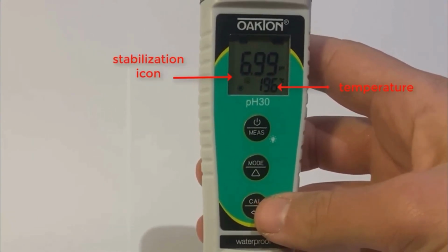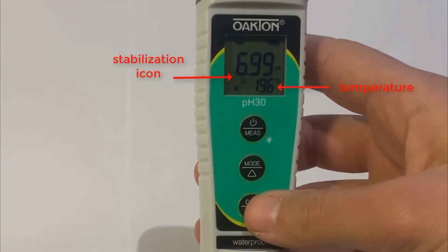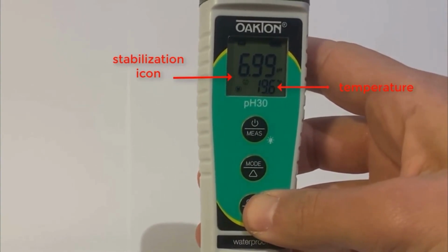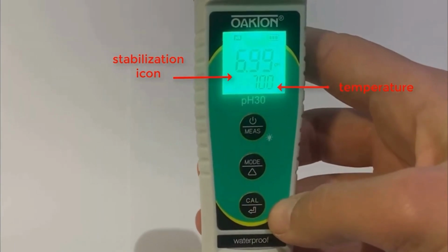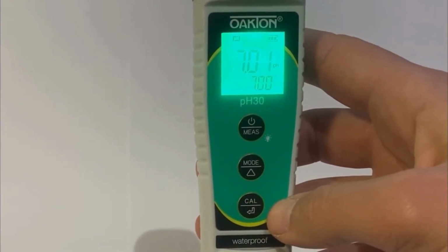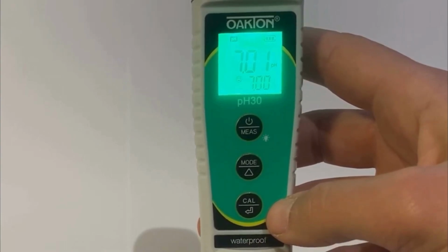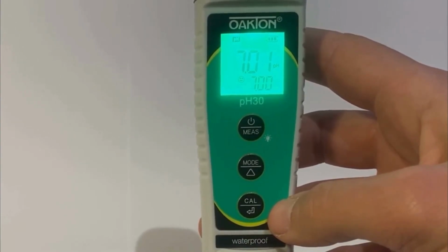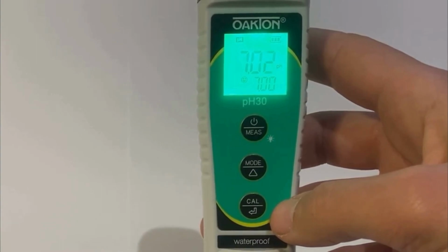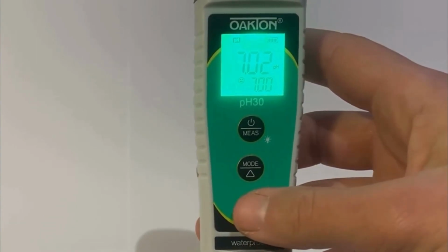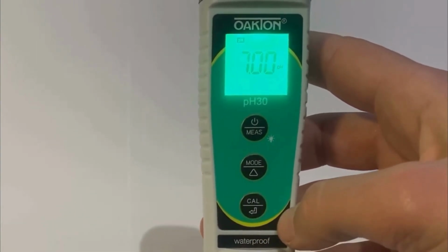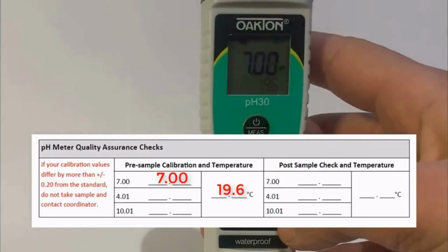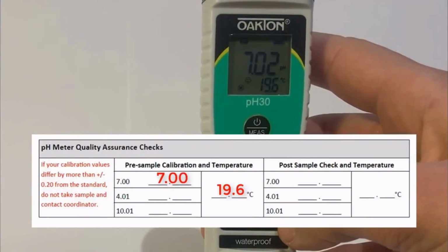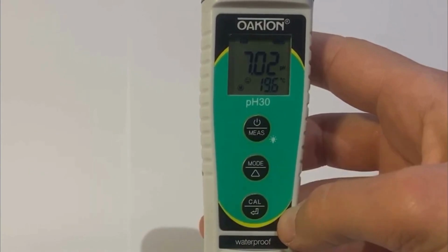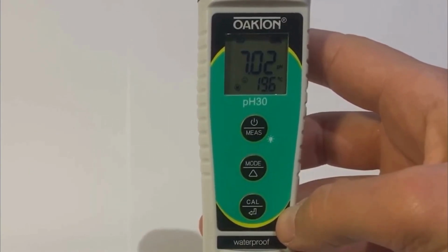Long press CAL, which is the bottom button, until your screen flashes CAL in green, and allow the stabilization icon to return. The bottom number should now read 7 when the meter recognizes which solution it is in. Short press CAL to enter this as your calibration. Record the number that flashes on your screen after you press CAL. The meter will now return into measurement mode.